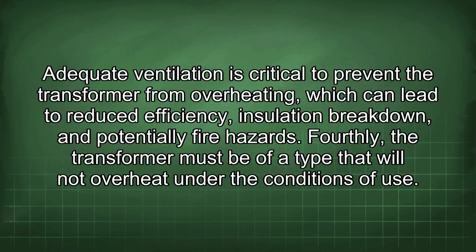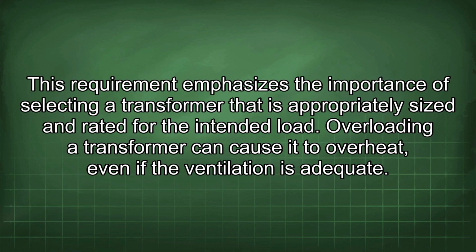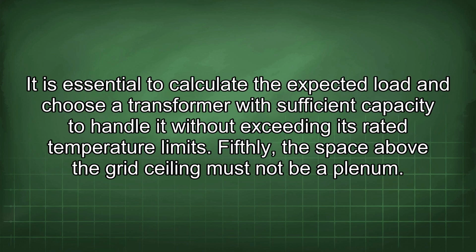Adequate ventilation is critical to prevent the transformer from overheating, which can lead to reduced efficiency, insulation breakdown, and potentially fire hazards. Fourthly, the transformer must be of a type that will not overheat under the conditions of use. This requirement emphasizes the importance of selecting a transformer that is appropriately sized and rated for the intended load. Overloading a transformer can cause it to overheat, even if the ventilation is adequate.